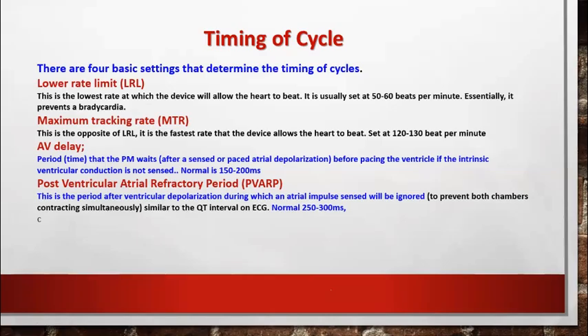Then the AV delay, that is the time the pacemaker waits after a sensed or paced atrial event. And the post-ventricular atrial refractory period is automatically adjusted in the pacemaker. This is the period after ventricular depolarization during which sensed atrial impulses will be ignored.